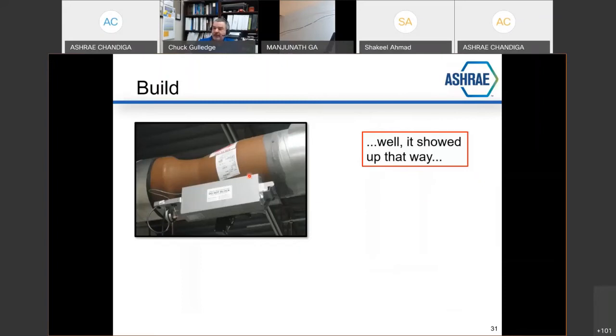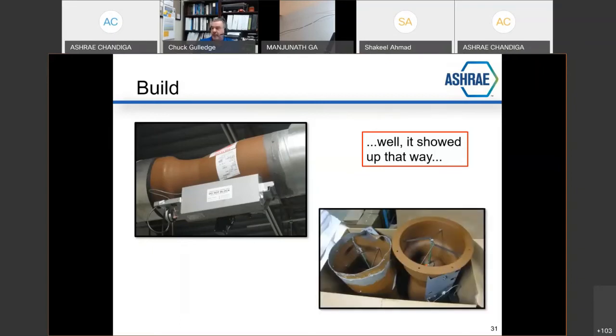This is a lab exhaust valve. You don't know whose it is, but you do know that it's got a Heresite coating on it. Look at this interesting scenario here. On this side, it's a slip fit. And on this side, somebody drove tech screws through the exhaust valve and compromised the Heresite coating. This was painful. This is what was supposed to be installed, flanged ends on this and this side. Every one of these, there were about 20 of these valves for this exhaust path.